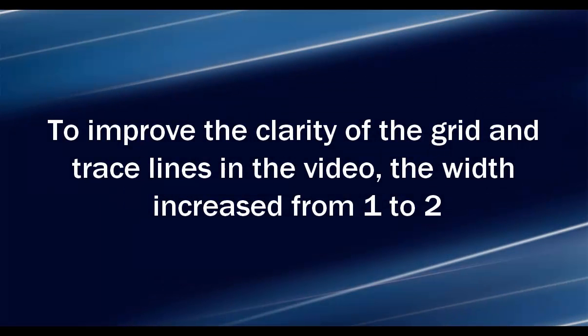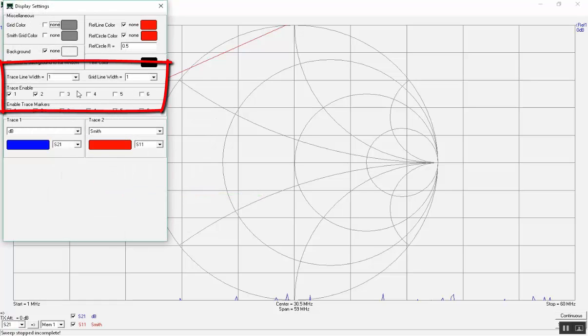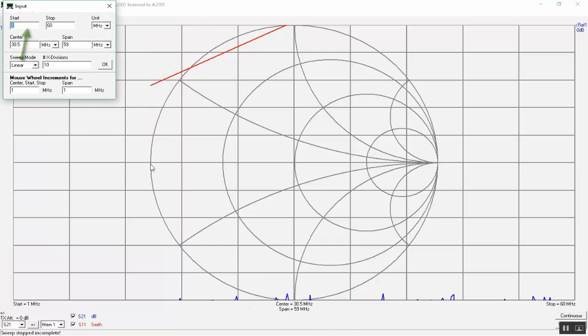To improve the clarity of the grid and trace lines in the video, the width is increased from one to two. Right-click on the window and choose trace options, then change the width from one to two for both lines. Before calibration we change the frequency span: start frequency set to one megahertz and stop frequency to 60 megahertz. Close by clicking OK.